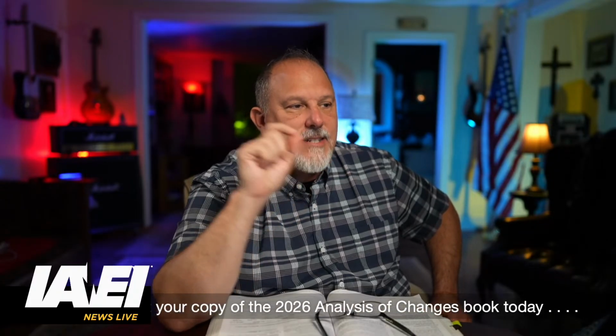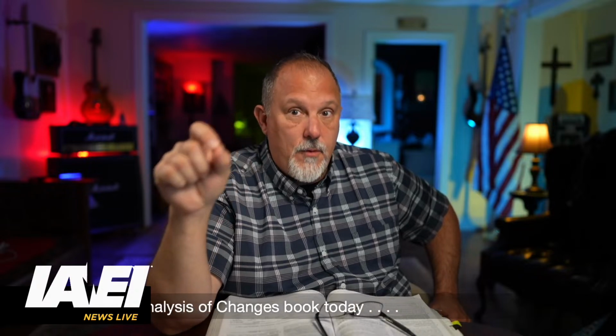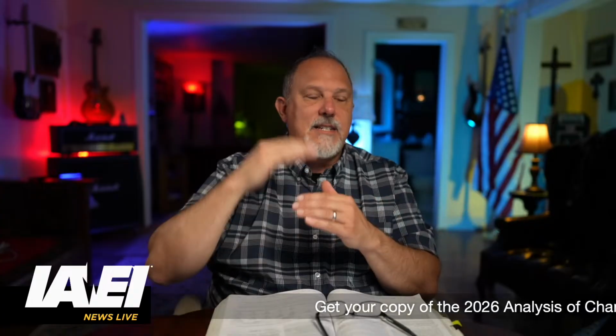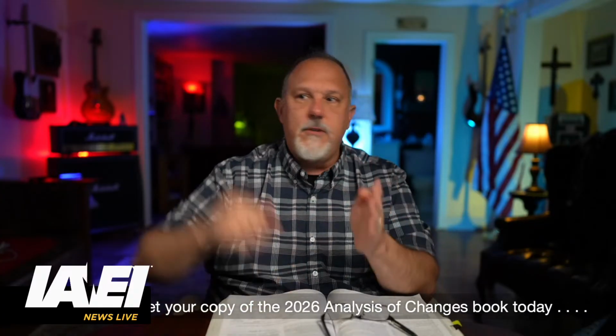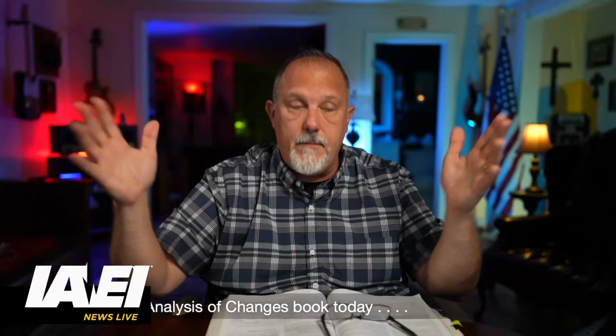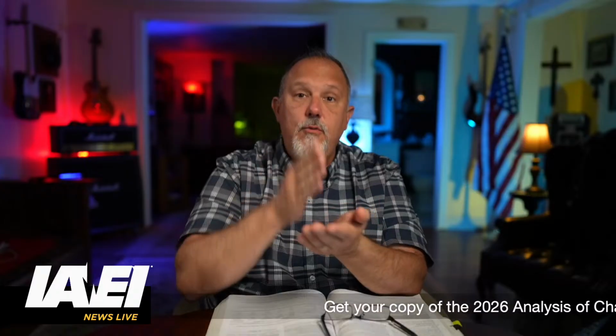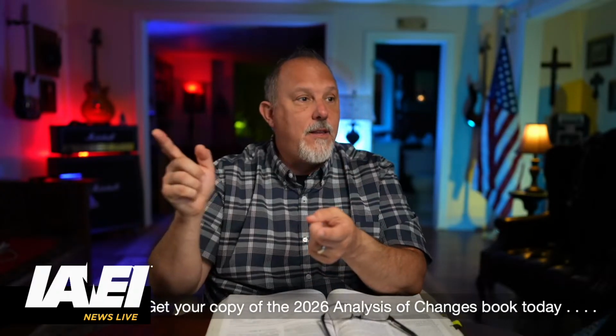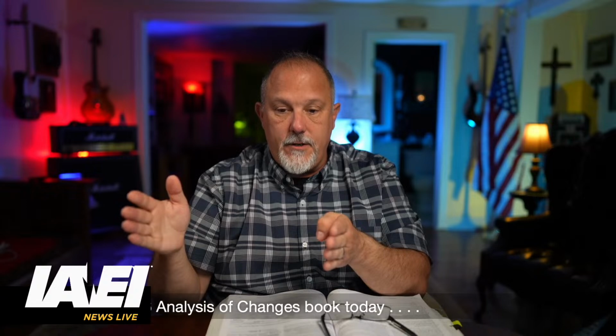But when you see the next higher commercially available, that means that if I look at a manufacturer's list of what they offer, and let's say the next standard ampere rating goes from 100 to 200, just making numbers up. Let's say it goes from 100 to 200 and you're at 145. If the manufacturer makes 150, you got to go to that one, not the standard ampere, which would be 200. Make sense? So now what's Dawn saying?